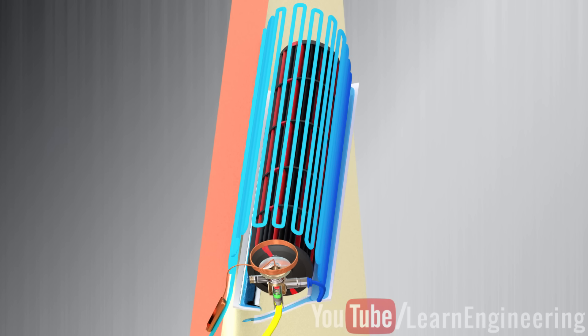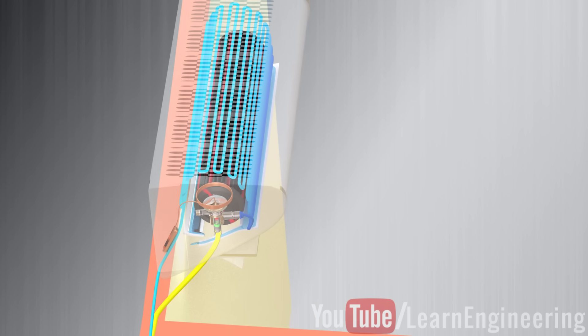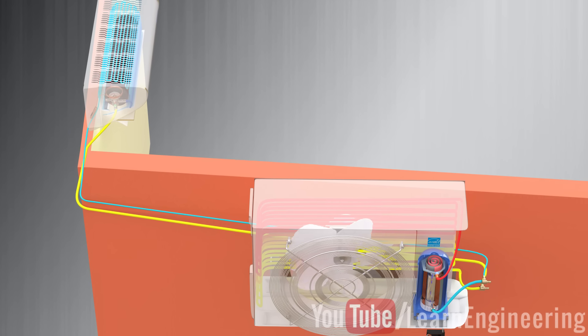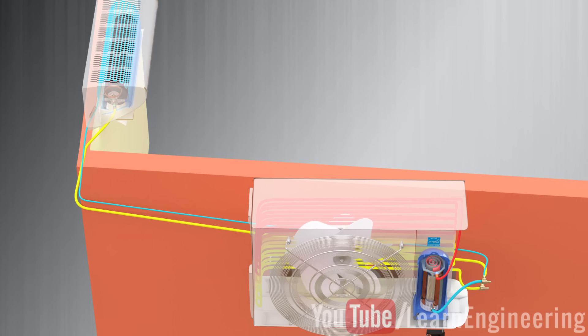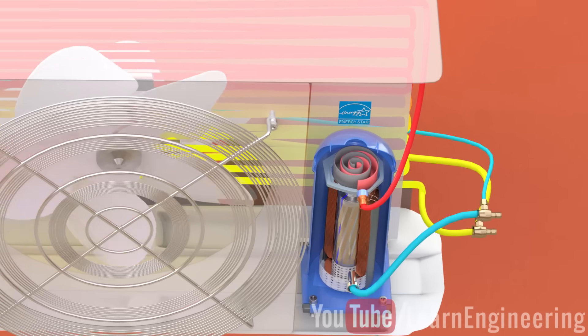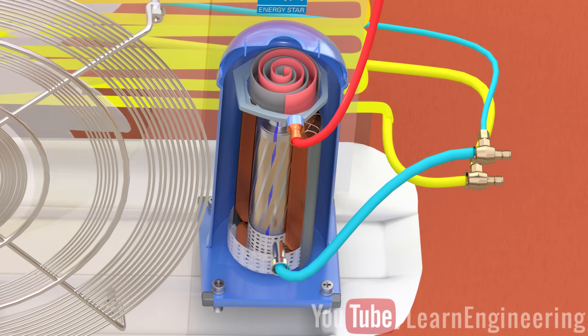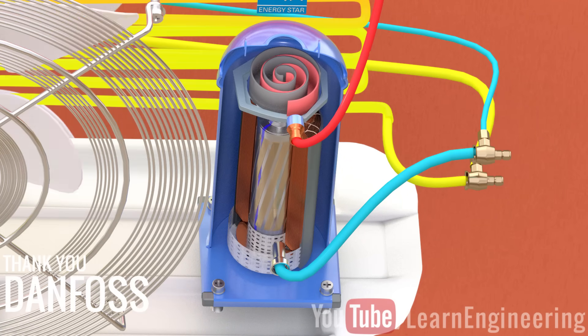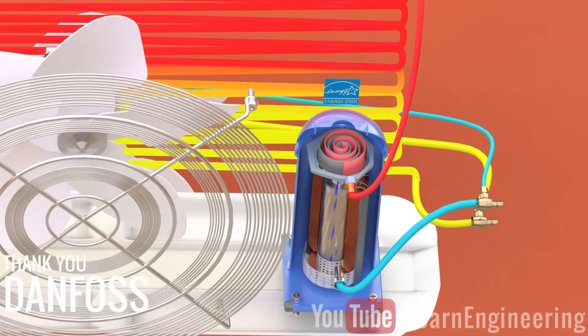Let us clear up a common misconception at this stage. TXVs do not control the room temperature. They just make sure that the compressor receives the refrigerant in pure vapor form. The refrigerant flow rate and the room temperature are controlled by the speed of the compressor. Due to their simplicity and efficiency, TXVs are widely used in the industrial and domestic applications.